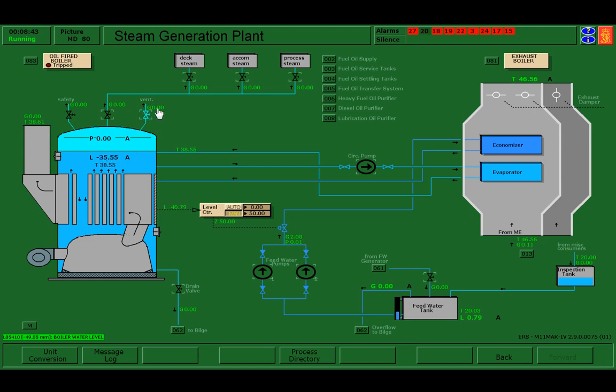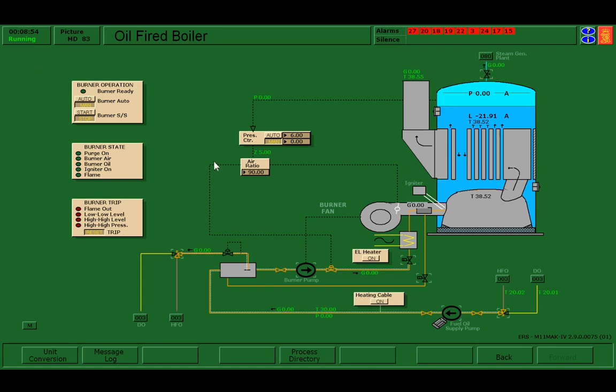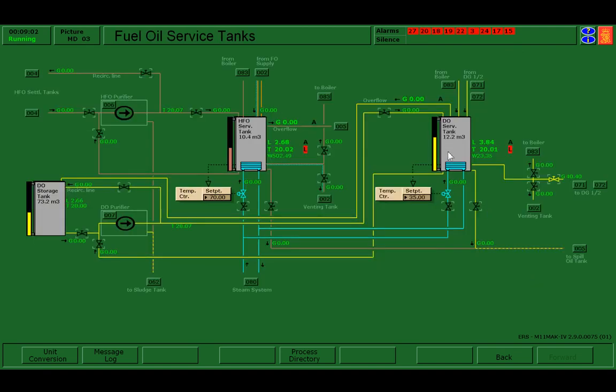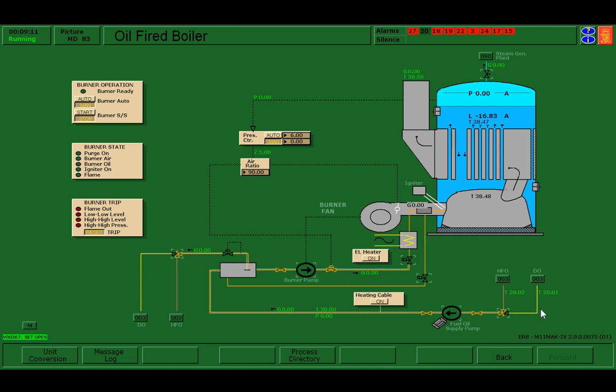I'm going to double check, make sure my vent is open. We'll need that during the startup. And I'm going to continue on to page 83, my boiler combustion page. So from the fuel side, I'm going to start at my diesel oil tank, follow my pathway to the boiler. I've got a valve here to open up. Make sure that my valves are aligned. I've got to make a change here to align to diesel oil, and return to the diesel oil tank. Turn on my fuel oil supply pump, and double check that my pressure controller is in manual at a low firing rate, somewhere 0 to 10%.